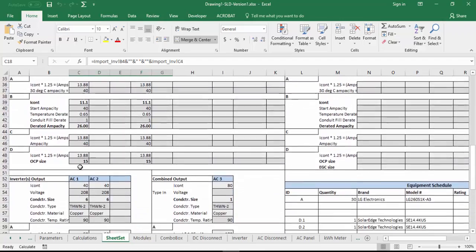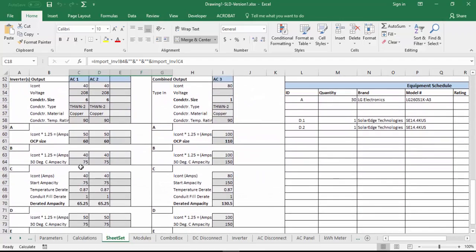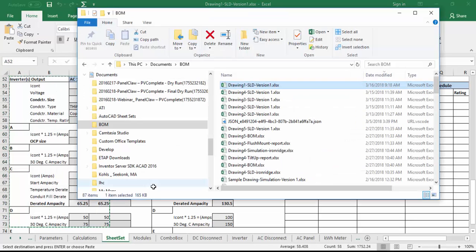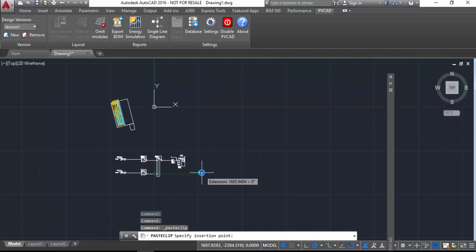There's a bunch of tabs here in this Excel spreadsheet, but the important one is the sheet set tab. That's where all the results of the calculations are displayed in an organized fashion. And what I like to do is find the relevant sections of this spreadsheet and I usually copy them and paste them back into my drawing so I can show the math that was used to generate the wire sizing and such for my drawing.